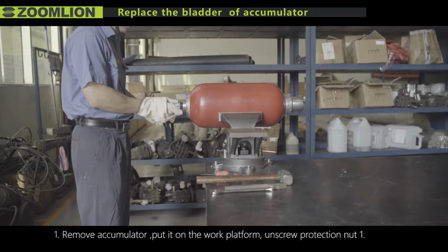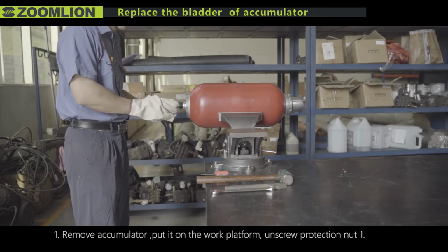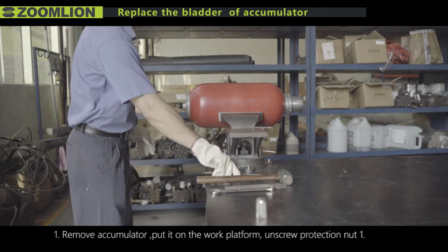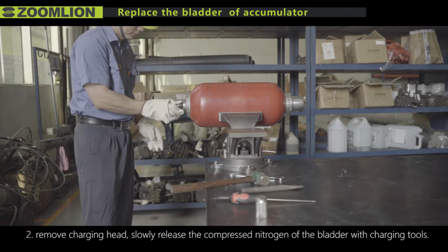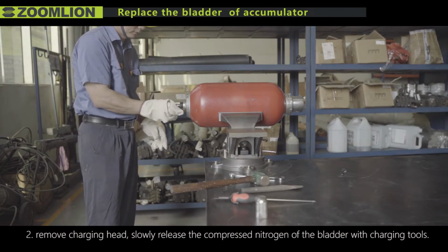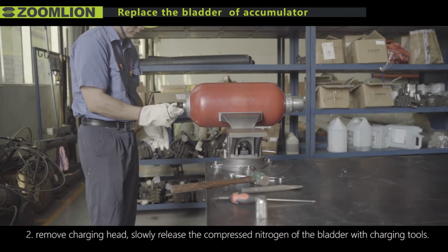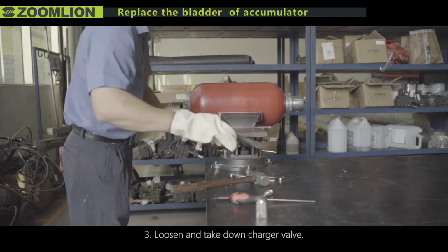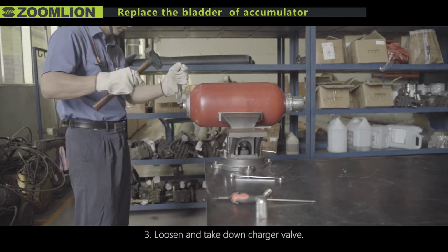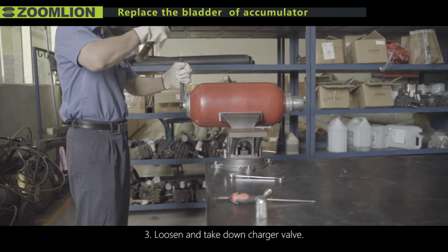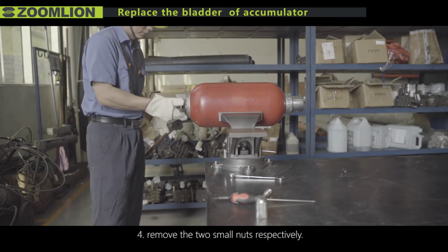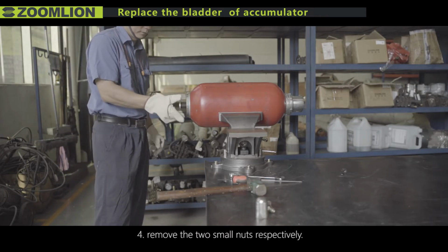First, remove accumulator. Put it on the work platform. Unscrew protection nut. Second, remove charging head. Slowly release the compressed nitrogen of the bladder with charging tools. Third, loosen and take down charger valve. Fourth, remove the two small nuts respectively.